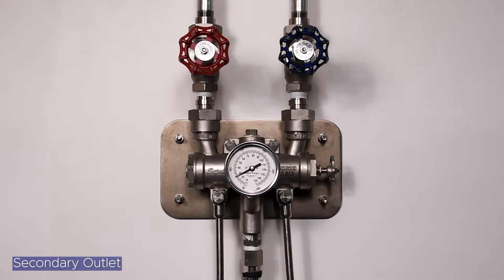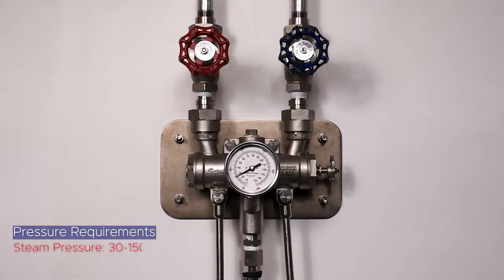This great feature allows factories to pipe in a secondary station that will operate at the same water temperature that exits the Duramix 8000's primary outlet. This unit requires steam pressure of 30 psi to 150 psi and water pressure of 30 psi to 150 psi.